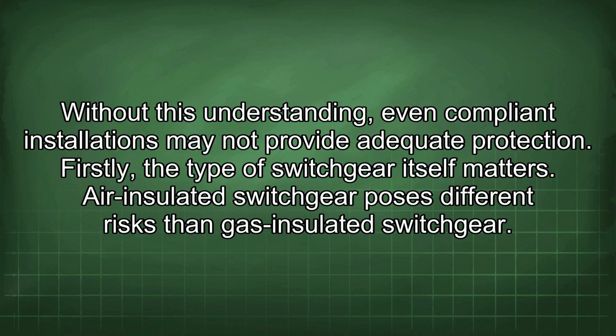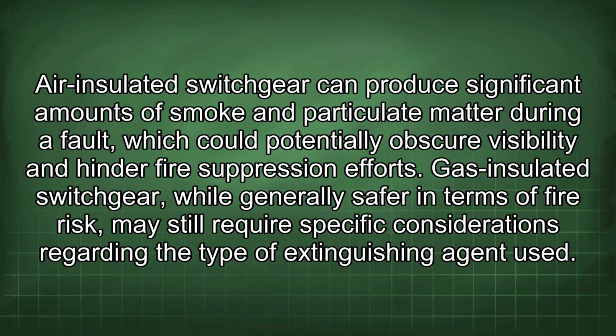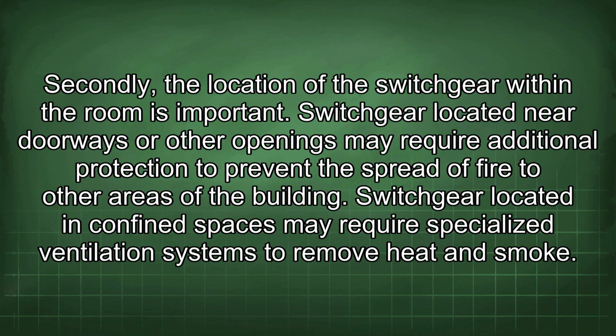Firstly, the type of switchgear itself matters. Air-insulated switchgear poses different risks than gas-insulated switchgear. Air-insulated switchgear can produce significant amounts of smoke and particulate matter during a fault, which could potentially obscure visibility and hinder fire suppression efforts. Gas-insulated switchgear, while generally safer in terms of fire risk, may still require specific considerations regarding the type of extinguishing agent used. Secondly, the location of the switchgear within the room is important. Switchgear located near doorways or other openings may require additional protection to prevent the spread of fire to other areas of the building. Switchgear located in confined spaces may require specialized ventilation systems to remove heat and smoke.